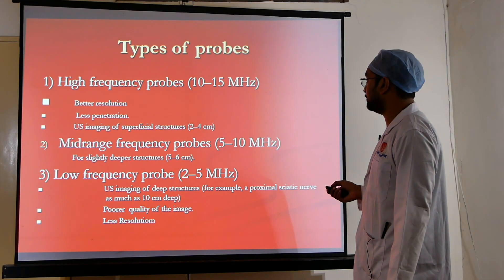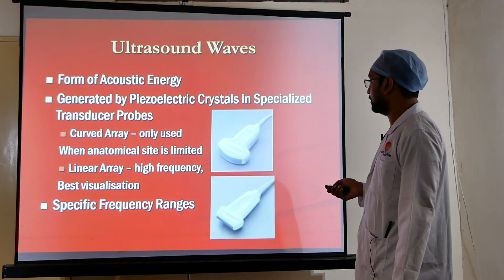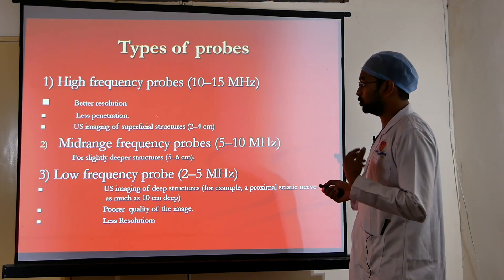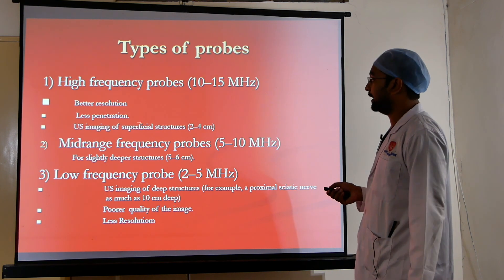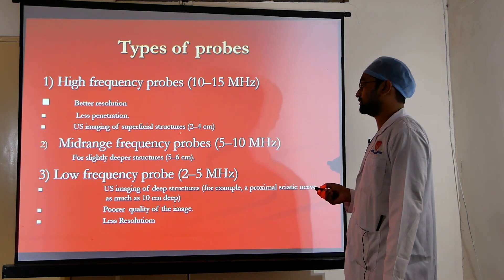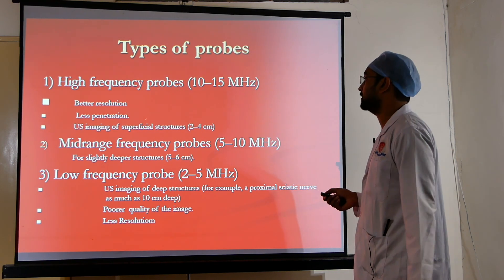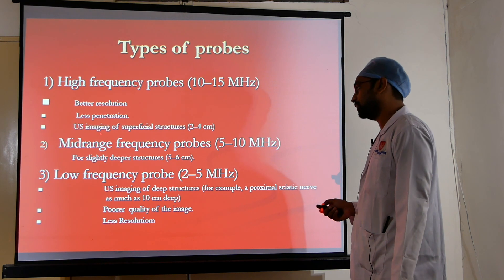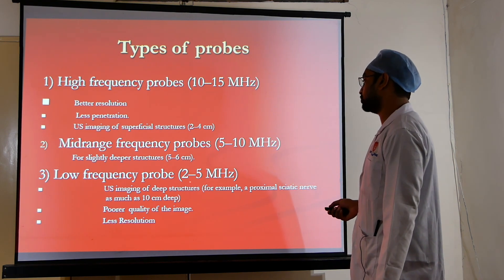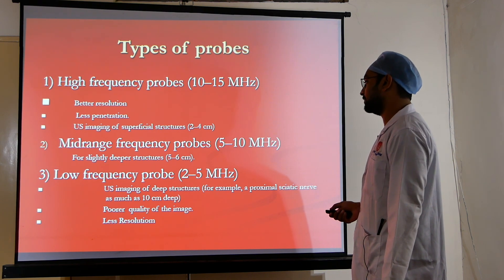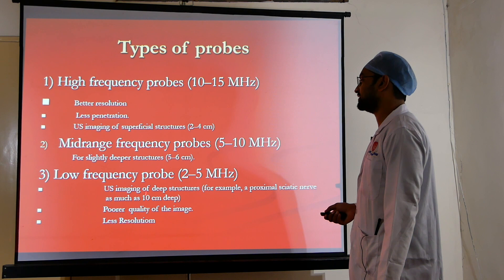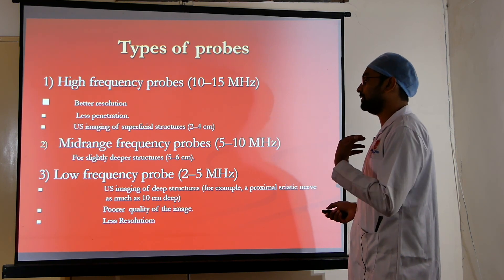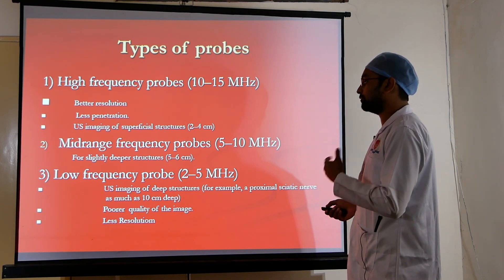High frequency probes give better image resolution but less penetration, used for superficial structures limited to 2 to 4 centimeters from the skin surface. Mid-range frequency probes at 5 to 10 megahertz are for slightly deeper structures up to 5 to 6 centimeters. Low frequency probes at 2 to 5 megahertz are used for imaging deep structures, for example a proximal sciatic nerve as deep as 10 centimeters, but produce poorer image quality with less resolution.